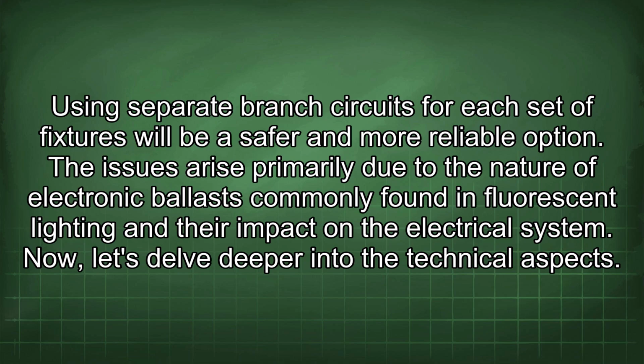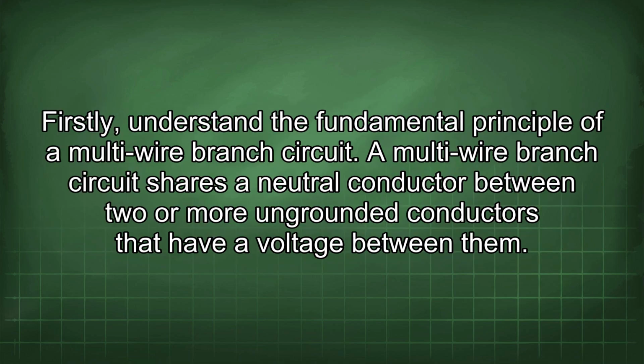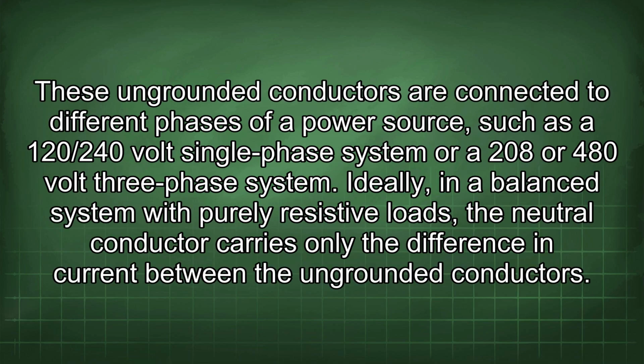The issues arise primarily due to the nature of electronic ballast commonly found in fluorescent lighting and their impact on the electrical system. Now let's delve deeper into the technical aspects. Firstly, understand the fundamental principle of a multi-wire branch circuit. A multi-wire branch circuit shares a neutral conductor between two or more ungrounded conductors that have a voltage between them. These ungrounded conductors are connected to different phases of a power source, such as a 120/240 volt single-phase system or a 208 or 480 volt three-phase system.